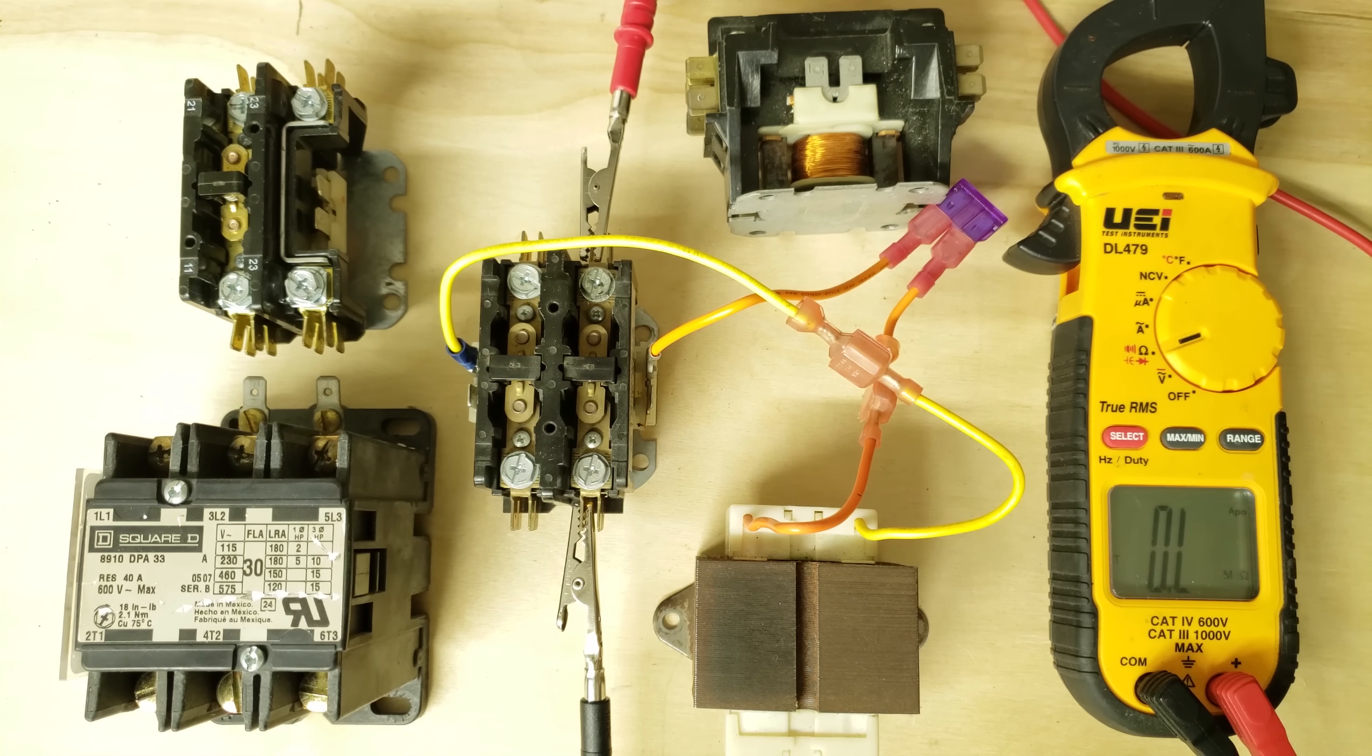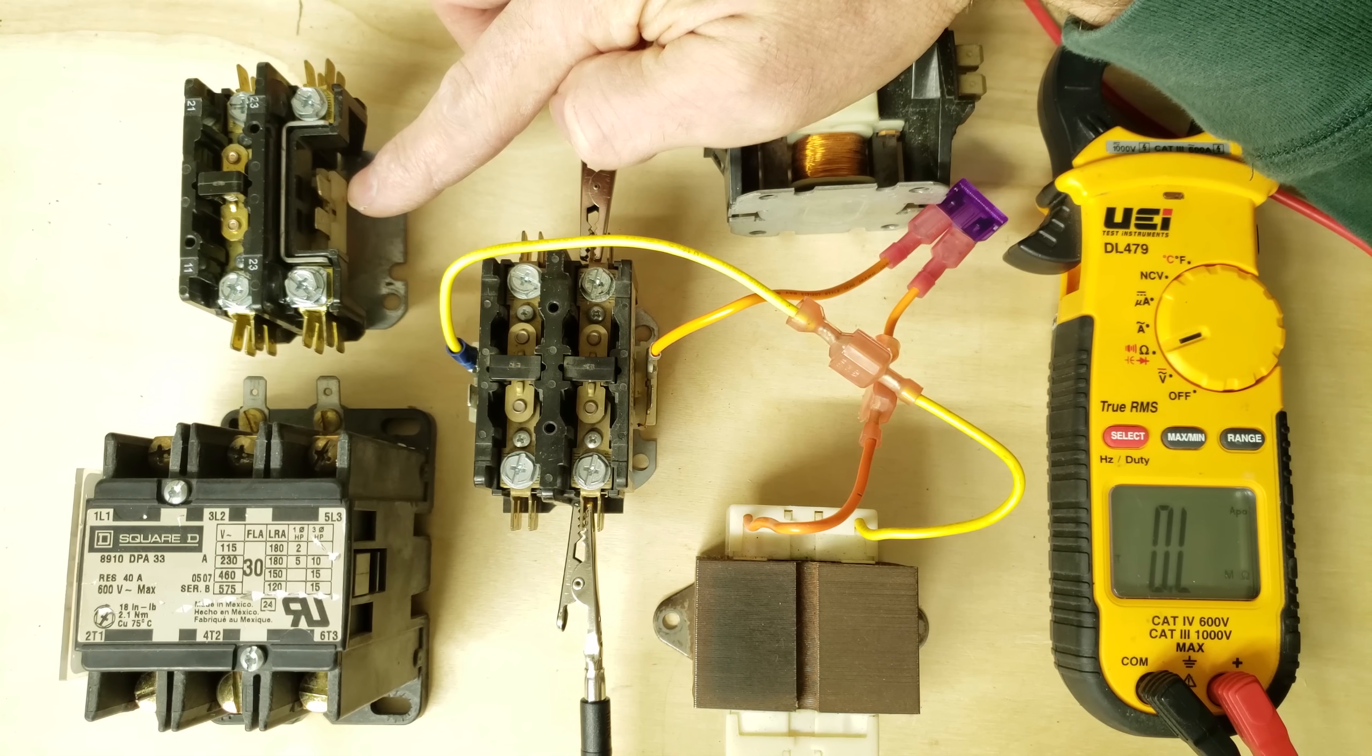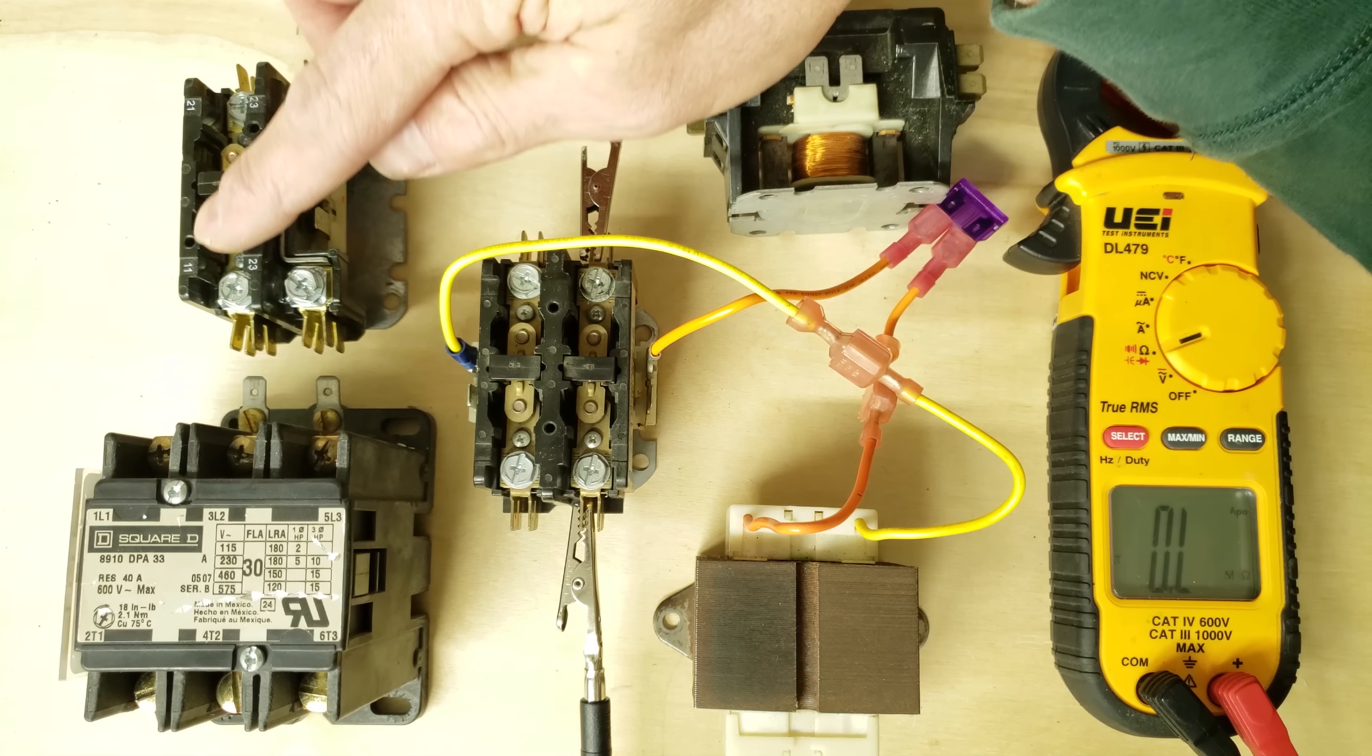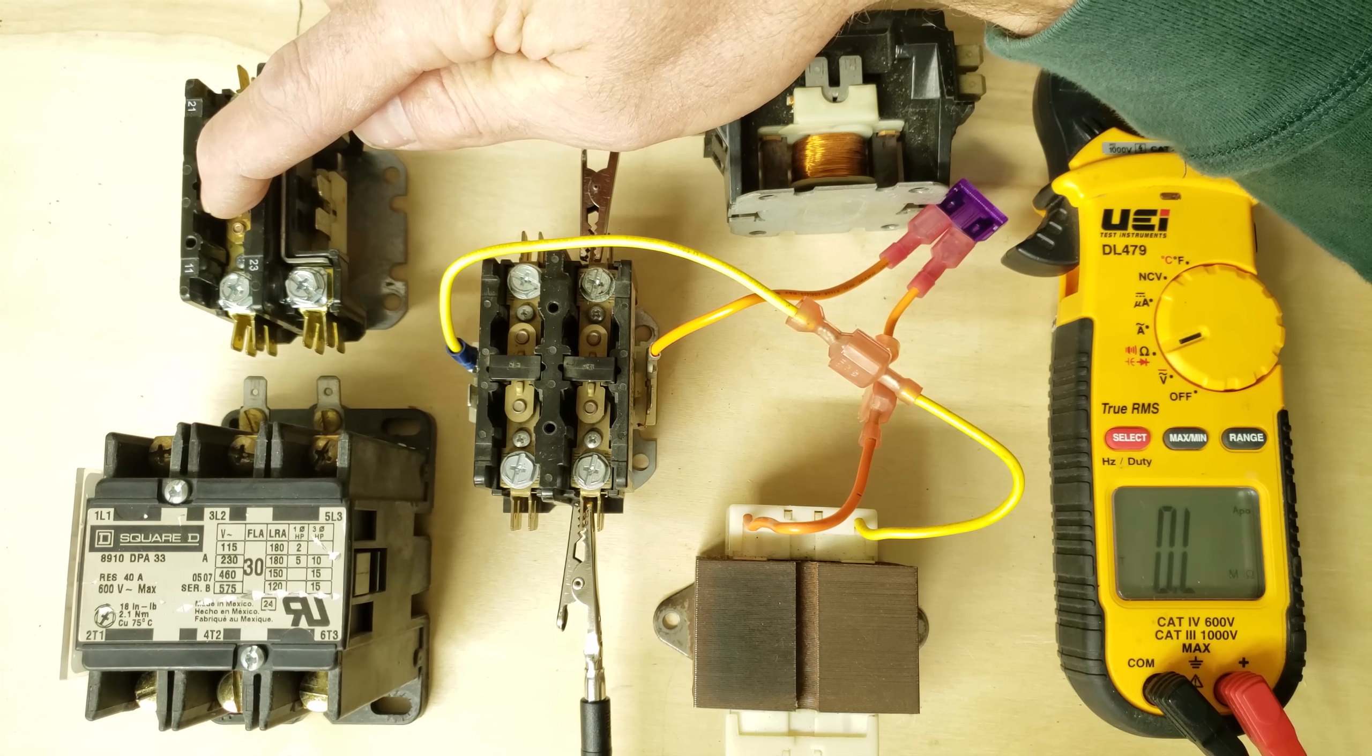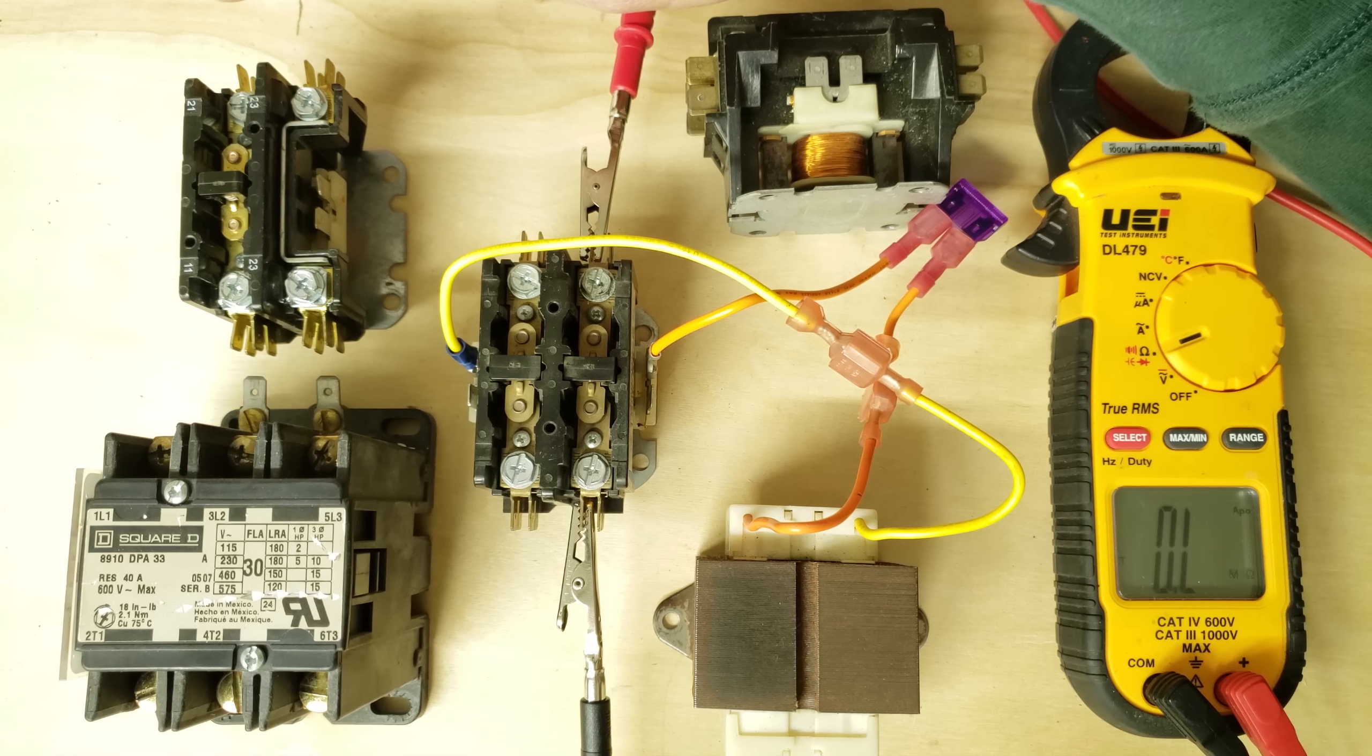The higher the FLA rating the stronger the electrical magnet has to be. So when we apply 24 volts on the side of this, if this one has a high FLA rating it needs to be able to suck that contact down even tighter to hold those contacts nice and tight for the high amperage running across it.